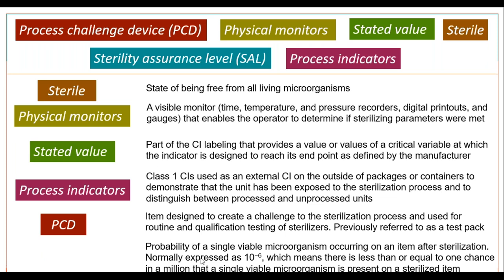Probability of a single viable microorganism occurring on an item after sterilization, normally expressed as 10 to the negative 6, meaning there is less than or equal to one chance in a million that a single viable organism is present on a sterilized item — and that's going to be our sterility assurance level.